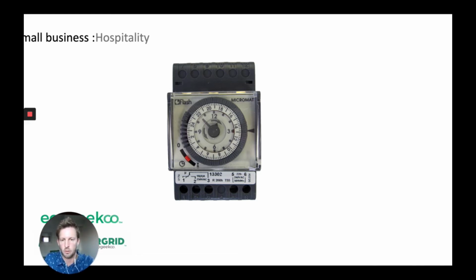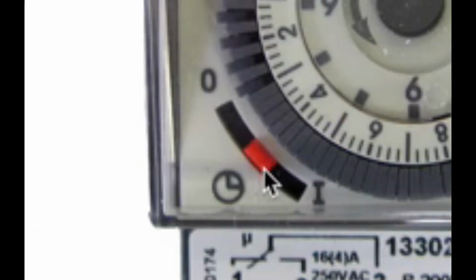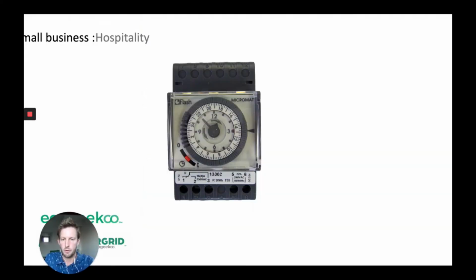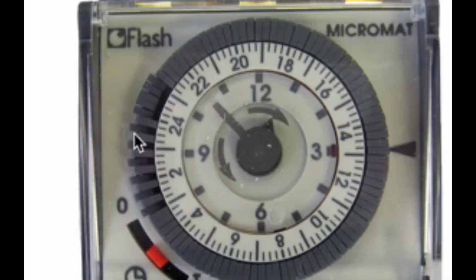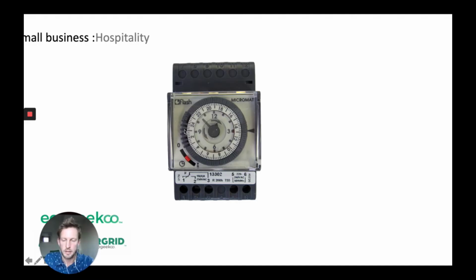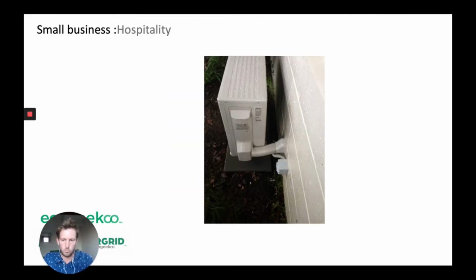So if you're sure that you don't need the thing that it's going to be running, you can just switch them off. So on this one, you can see here, you can either leave it to the I, which means it's going to be on the full time, or it's currently on time clock is where it's sat, or you can switch it to 0, and then that will switch it off. If you're unsure, you can push all these ones back in, but take a photo first so you can actually see when you come to reset it, how it was in its original position. So that's one little area.